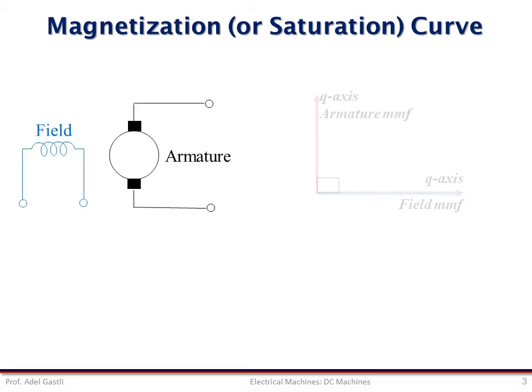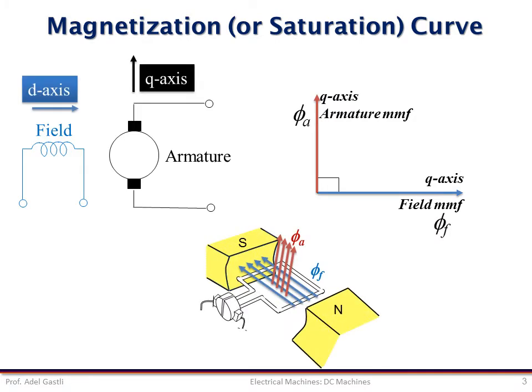A DC machine has two distinct circuits, a field circuit and an armature circuit. The magnetomotive forces produced by these two circuits are at quadrature, meaning they are perpendicular. The field MMF is along the direct axis D and the armature MMF is along the quadrature axis Q. Ideally it can be assumed that the armature MMF has no effect on the field flux on the D axis because the armature MMF acts along the Q axis.